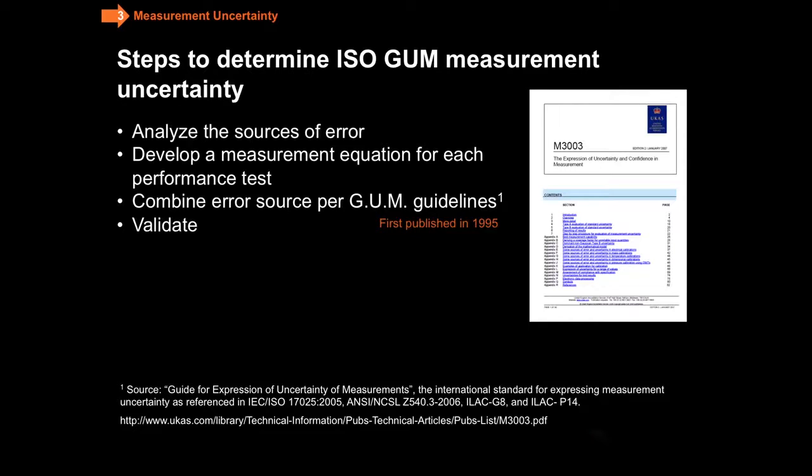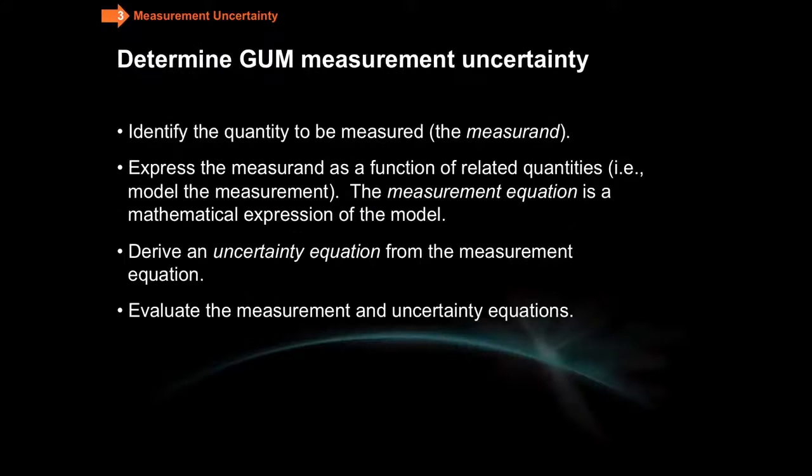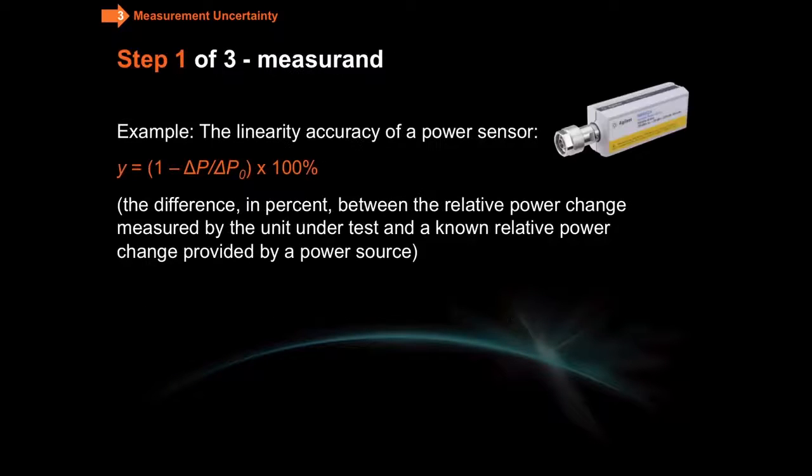If we dive in just a little bit more specifically, these would be the specific steps that you would take. We're going to take a power sensor, and we're going to take a fairly common measurement. Most power sensors have a linearity specification. The definition of power linearity is really just the difference in percent between a relative change of a known change by a reference power source and the amount that you measure with the power sensor itself.